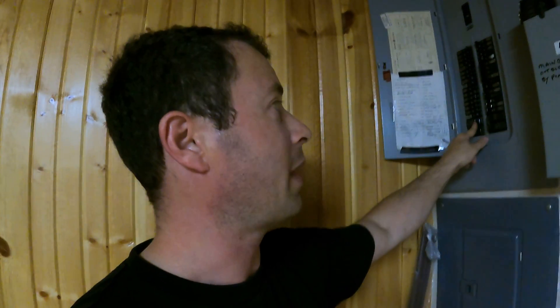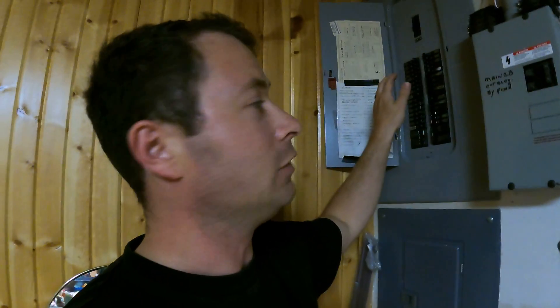I'll turn off my backup whole-house generator, and then I'll turn off my main. Now my main is off, but my barn comes in through here on a 100-amp service. I'll back-feed from the barn to this panel. The way it works is this is just a metal connection — when I create power out at the barn, it goes through that circuit and makes the whole bus bar live. Since it's 220V, it's both bus bars. For your house, you need a 220V circuit that's big enough — at least 50 amps. I have 100 amps here, but it's actually a 50-amp outlet out of the barn.